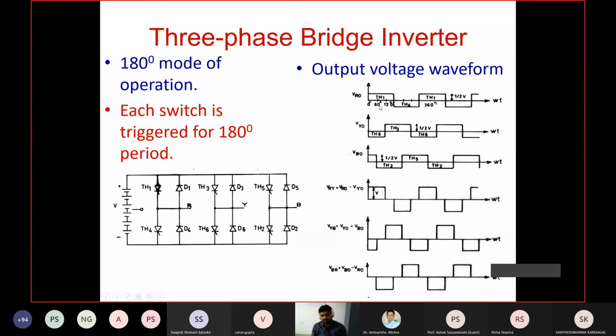How many levels you see in this pole voltage basically defines the level of the inverter. If you operate the same inverter in 180-degree mode, the output line voltage looks like a quasi square wave, with V, 0, and minus V. So just by seeing this output line voltage, you cannot say this inverter is 3-level.